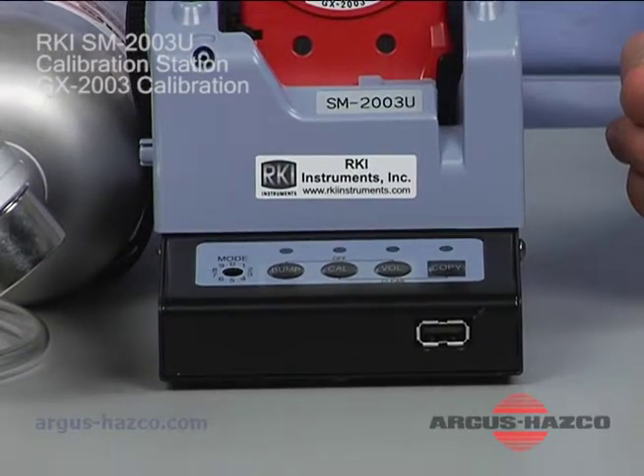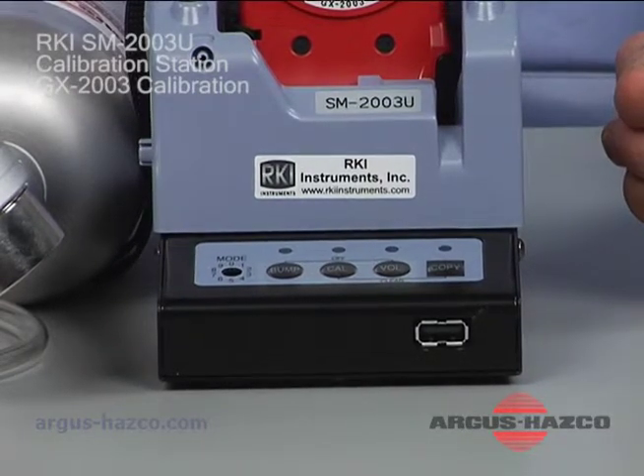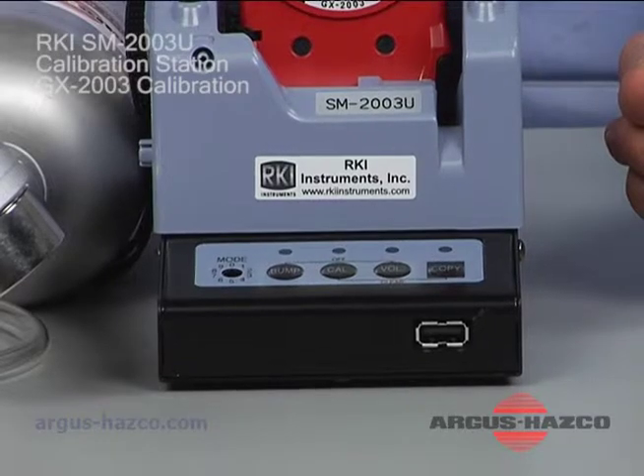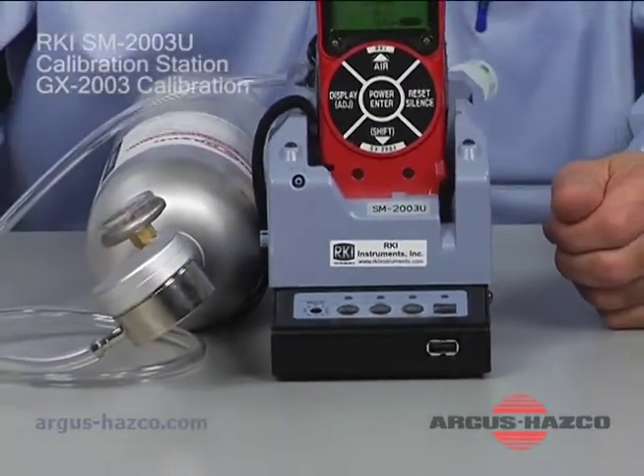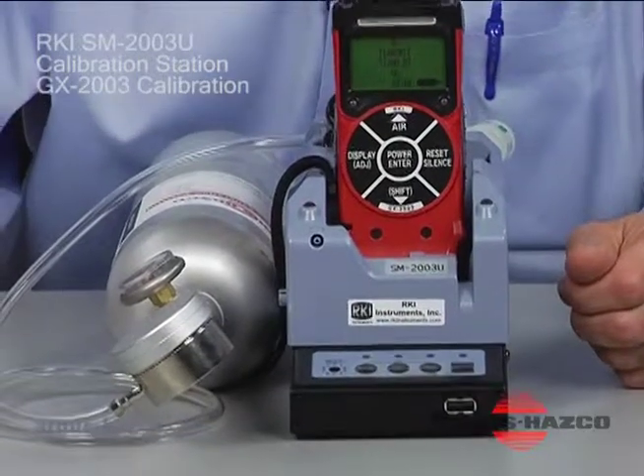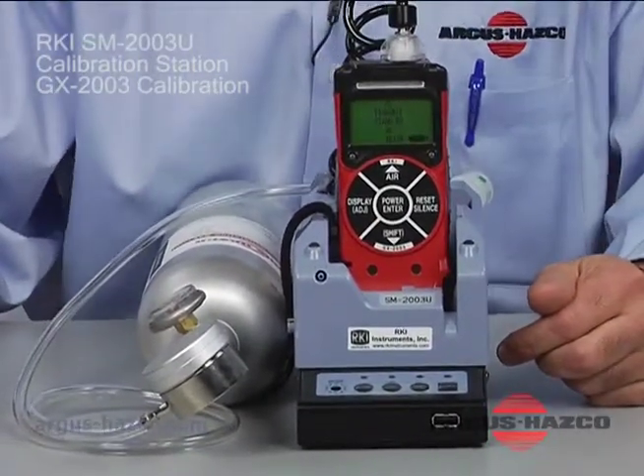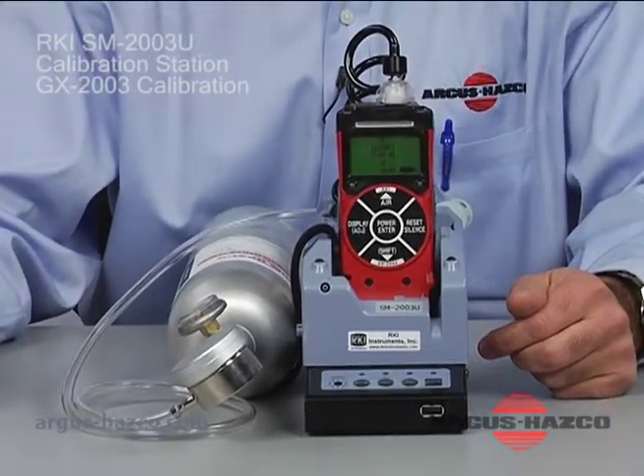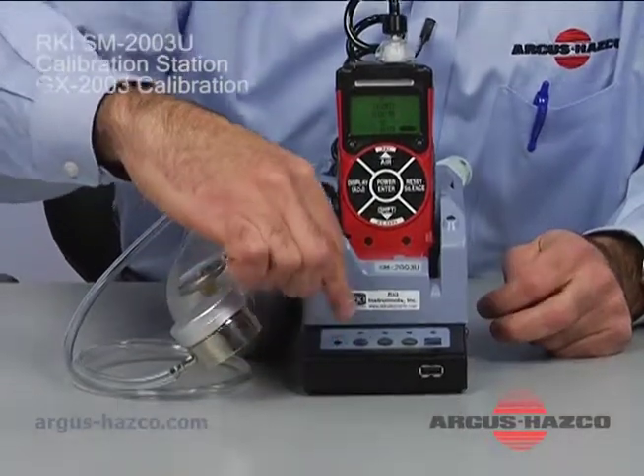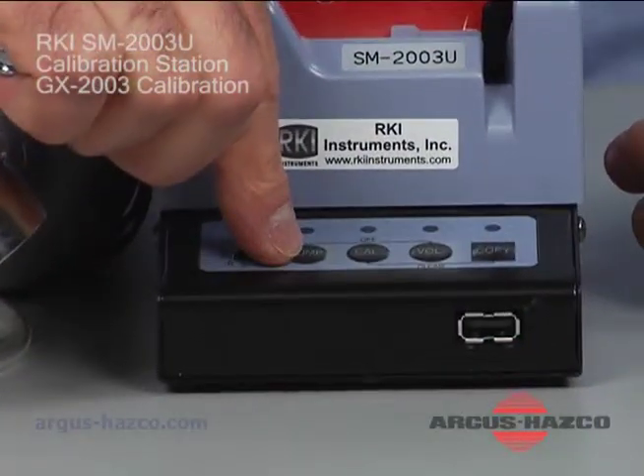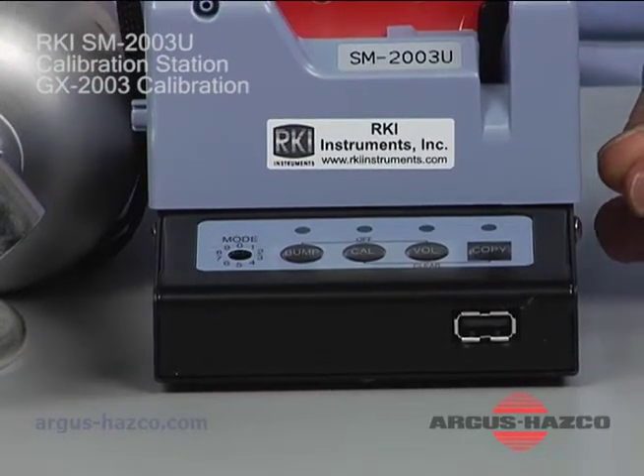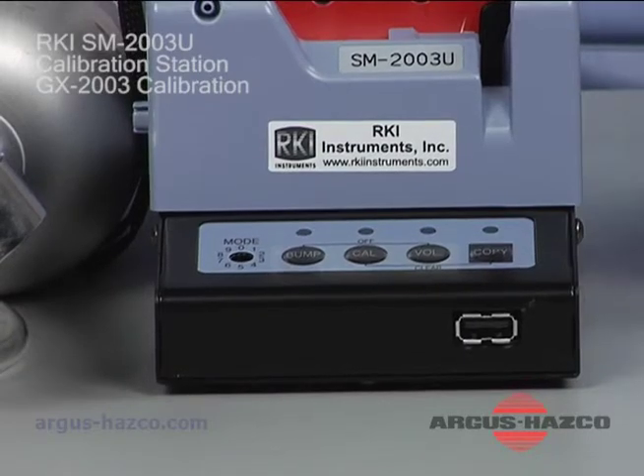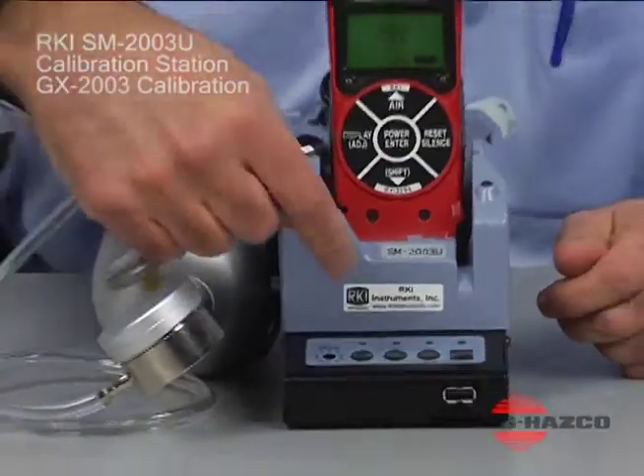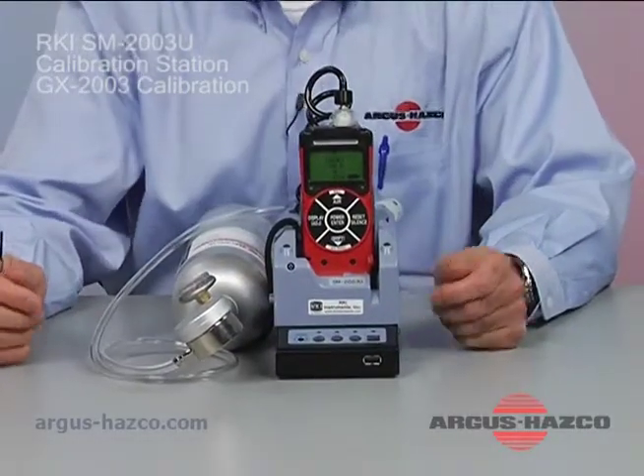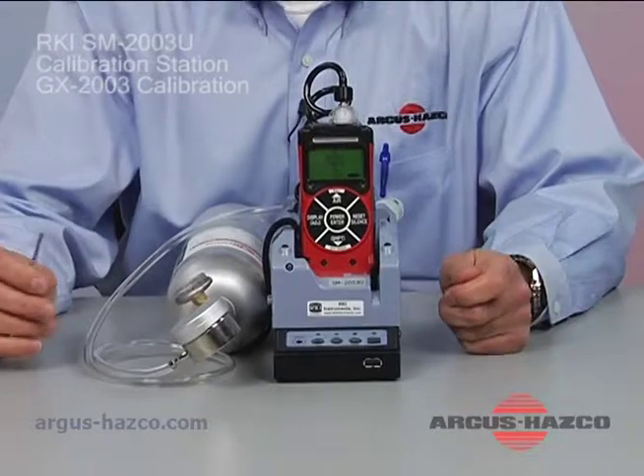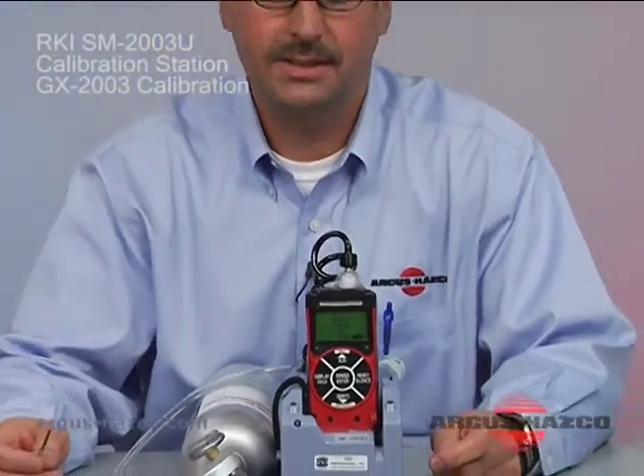But on position 6, we're going to flow gas to the monitor for a certain amount of time. The way it's set up is 30 seconds of clean air, 45 seconds of gas exposure, and then if it fails the bump, which I'll show you which buttons allow you to bump the instrument, it will automatically go to calibration. Okay? So if you're looking to bump the instrument itself, there is a button that's labeled bump, and we push the bump button, bumps the unit, and it will show up as pass if it passes without any failure on the sensors. If it fails, it will immediately go to cal without any buttons being pushed at that point. It's automatic, and that's why I prefer to set the switch position to 6.